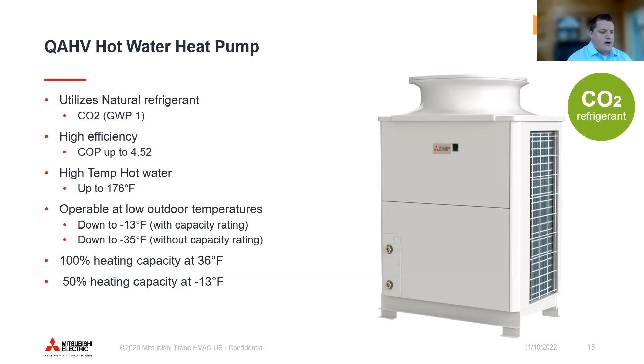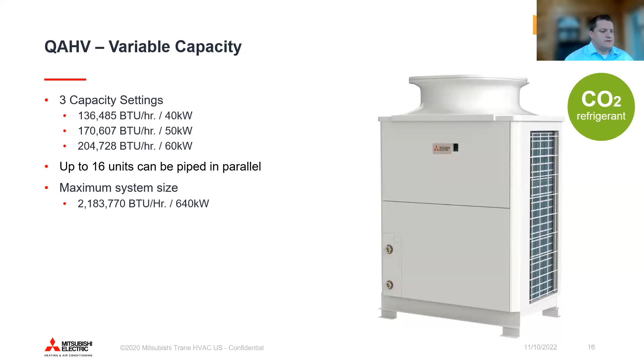So just some mile markers as to where our capacities are. It's 100% heating capacity at 36 degrees and around 50% at our cataloged -13-degree range. But then again, it will have that extended range down to -35 if needed. The unit itself has 3 different modes, but for all intents and purposes of sizing, we size around the 40 kW setting. The other settings are really ambient dependent, and they come into play when you start using demand response and some of the utility incentives that can come with that, of doing a load up scenario on the system. But for all of our sizing and critical sizing, the 40 kW is what we'll size to. You can do 16 of these units in parallel on a system, so a little over 2 million BTUs.